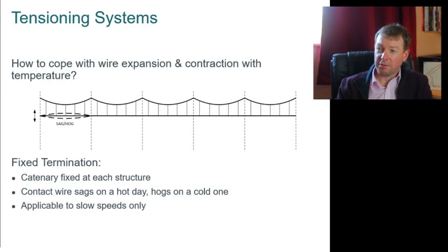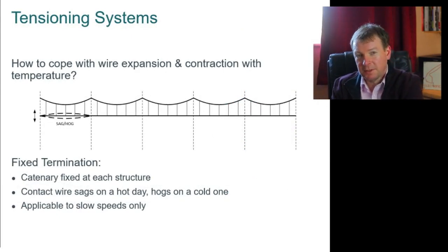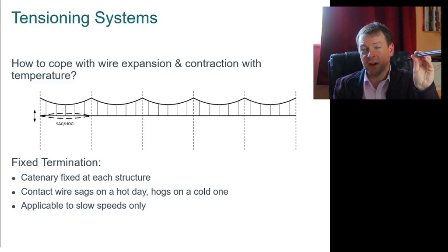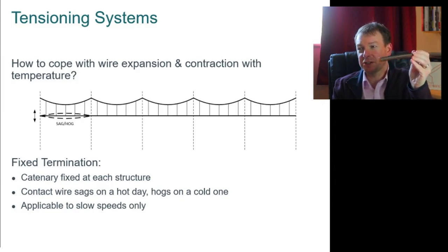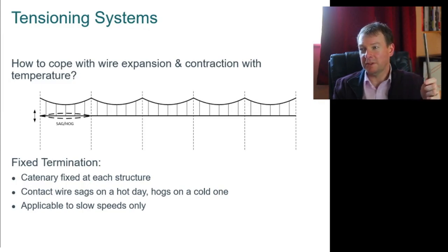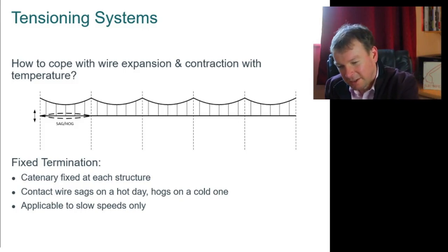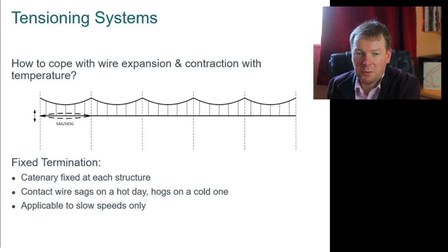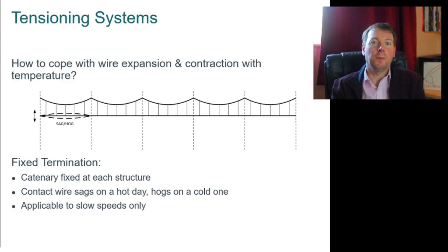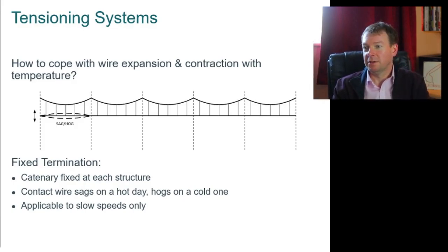Another big challenge we have is that this stuff's great electrically, and great mechanically, but from a thermal expansion and contraction point of view, it's not great. This stuff expands when it heats up and contracts when it cools down, and a typical overhead line system might have to cope with a 50 degree C operating range from a cold day to a hot day. So that means the whole system's expanding and contracting depending on time of day and time of year. So how do you deal with that?